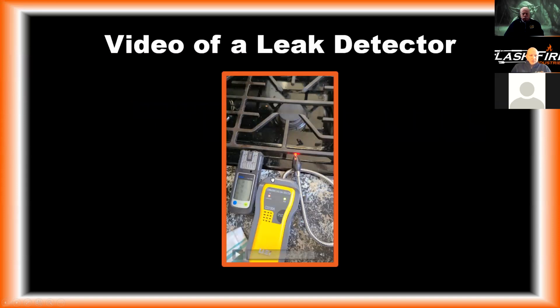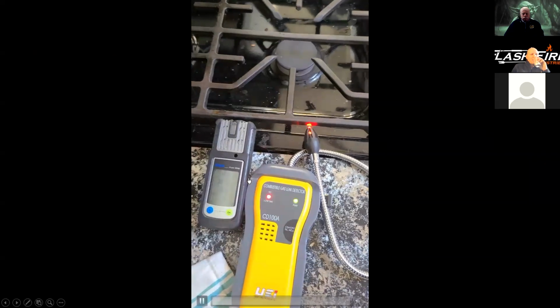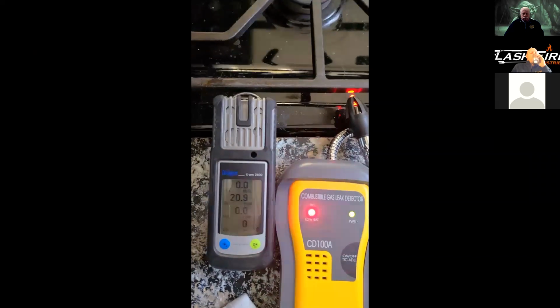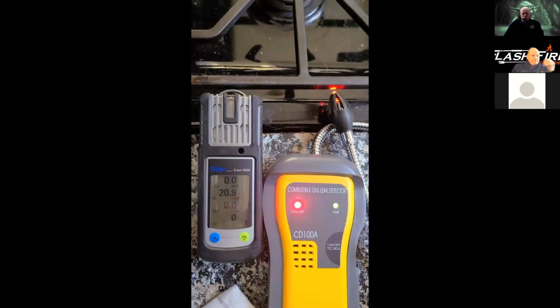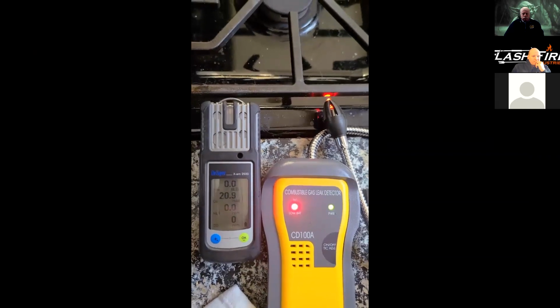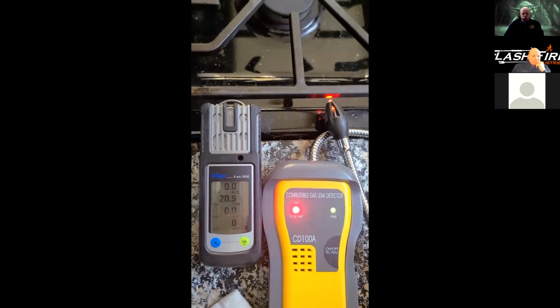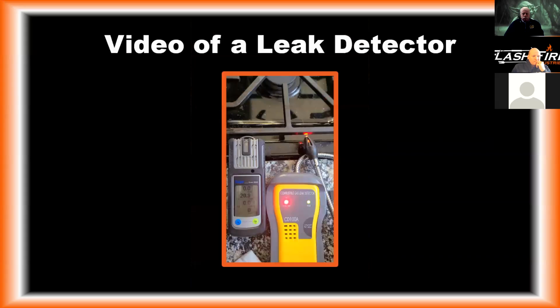So this is just a stove top example. I have my LEL meter on the left, my leak detector on the right, and you're going to see how the leak detector goes off. And actually, at no point through this does my LEL sensor. All right, so the leak detectors can be very useful for just that, leak detecting.